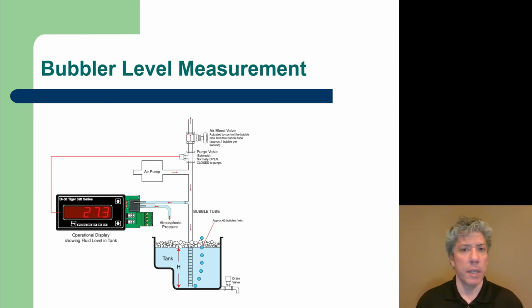Now, flow rates are not the only things to be measured. Level is another thing. This is a bubbler level type of measurement device. If you think about a volatile or explosive or flammable fuel, you probably don't want electronics near it that could possibly ignite a fire. You want the electronics for measuring the level in the tank to be remotely located to the tank, where you can ensure that they won't spark a flame. This is a fairly clever way of doing that. All that you really need is a bubbler tube down into the tank.